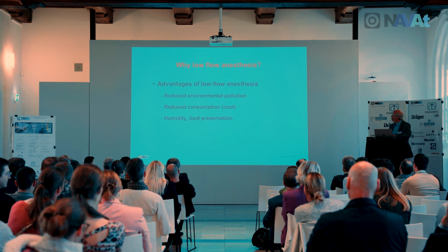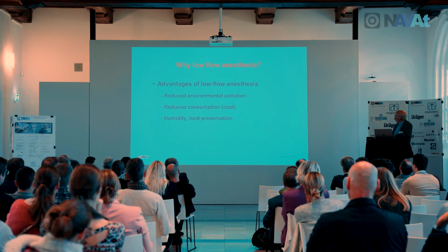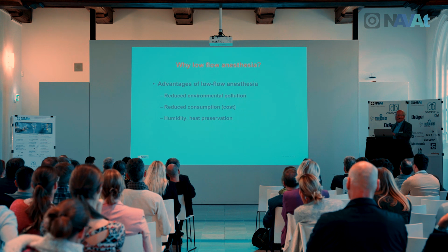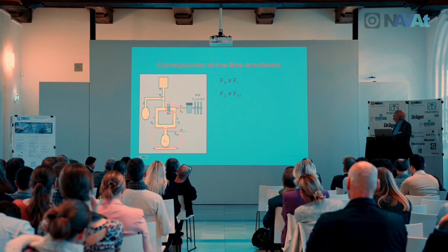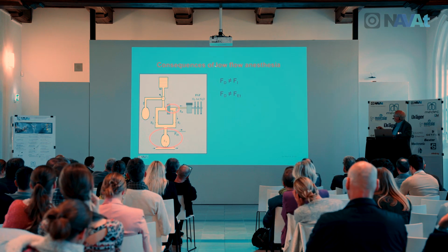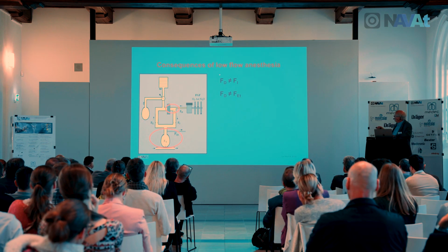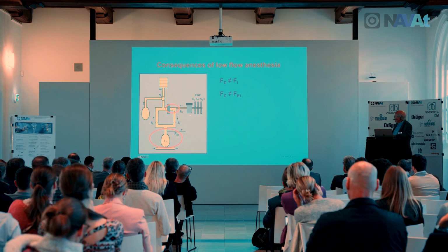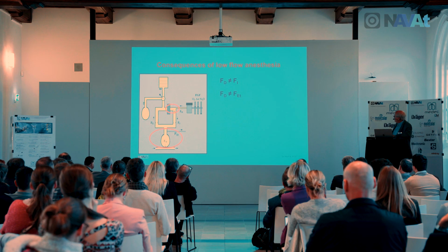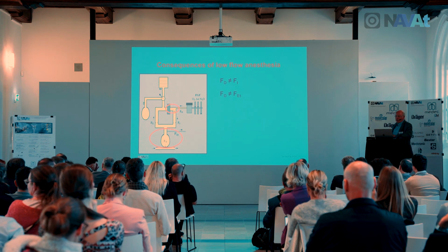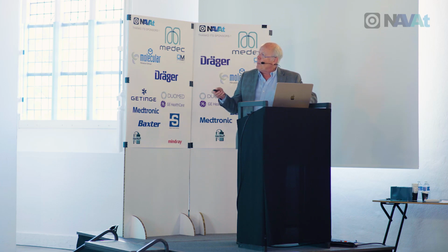Now low flow. What are the advantages of low flow? I'm not going to go over this, we all know this. What are the consequences of low flow anesthesia? The first consequence is that the vaporizer dial setting does not correspond anymore with the inspired partial pressure. And why is that?